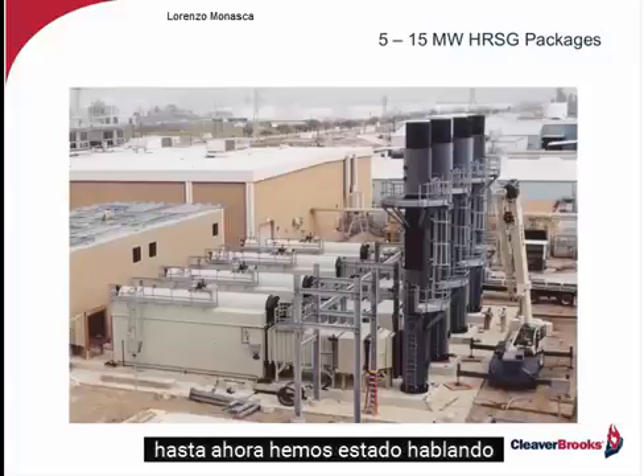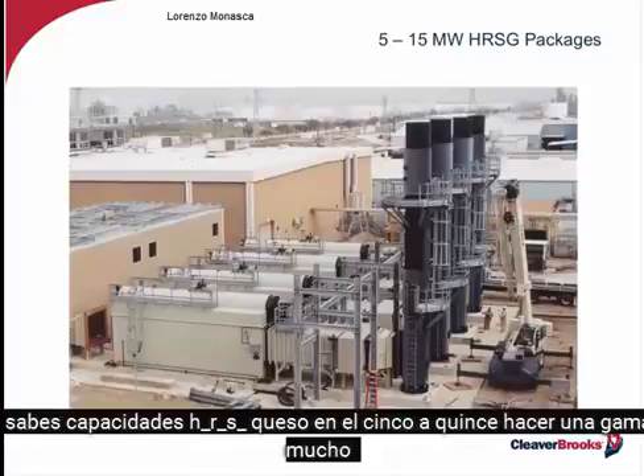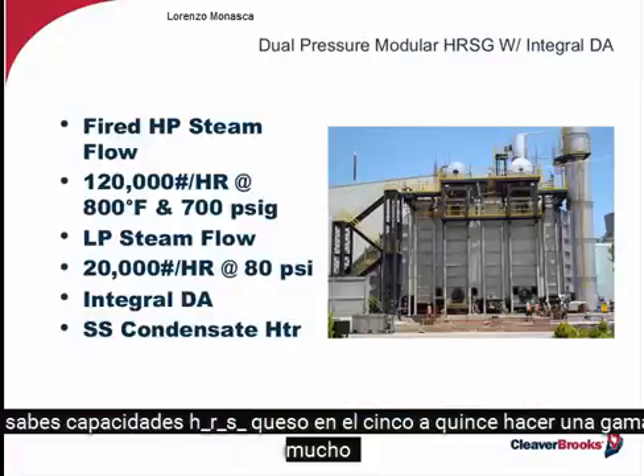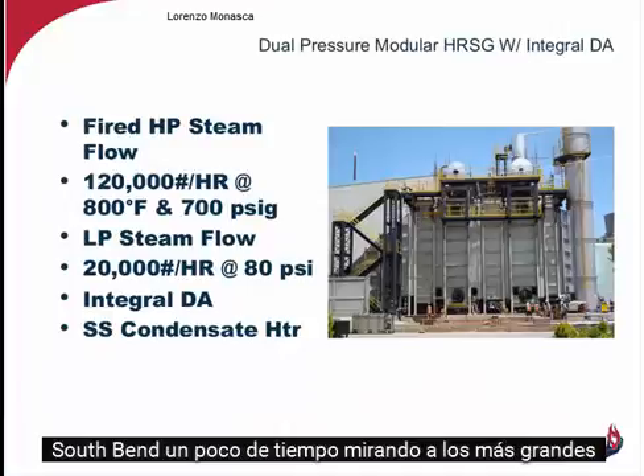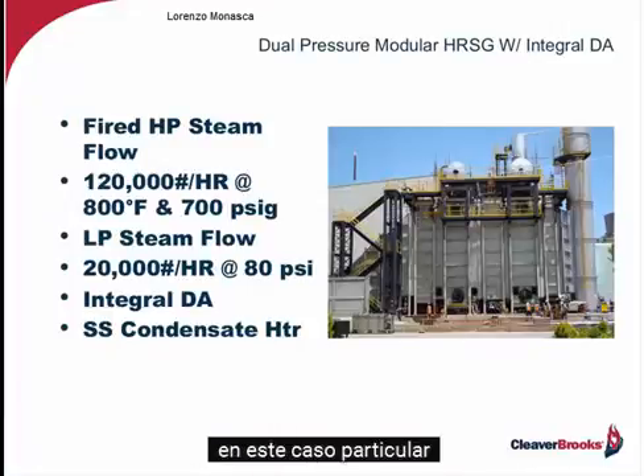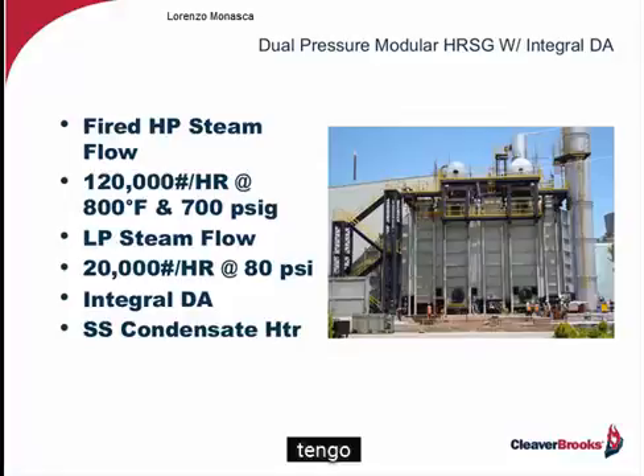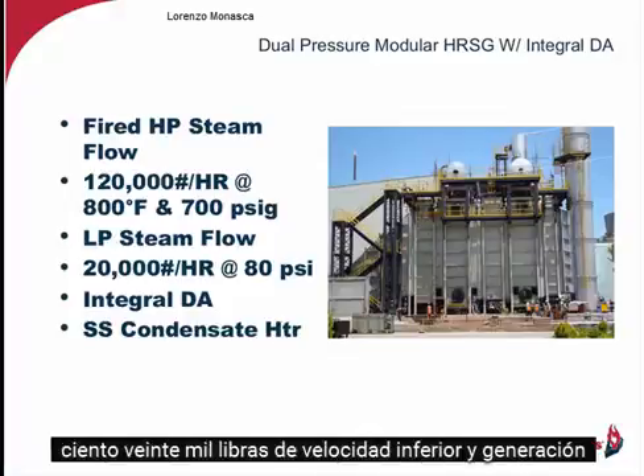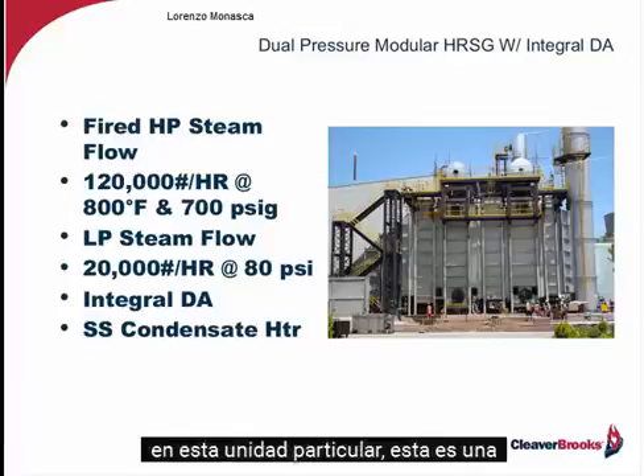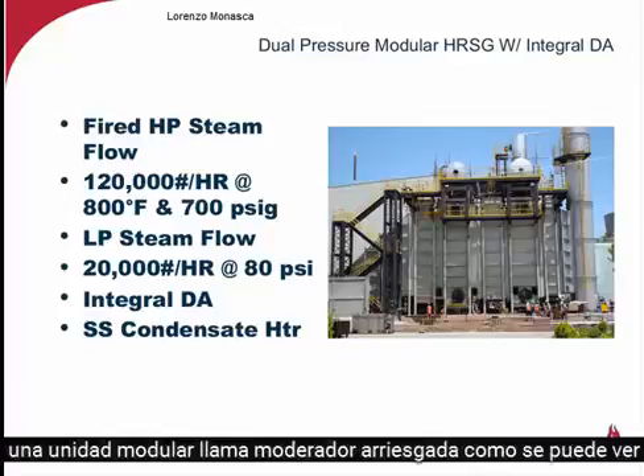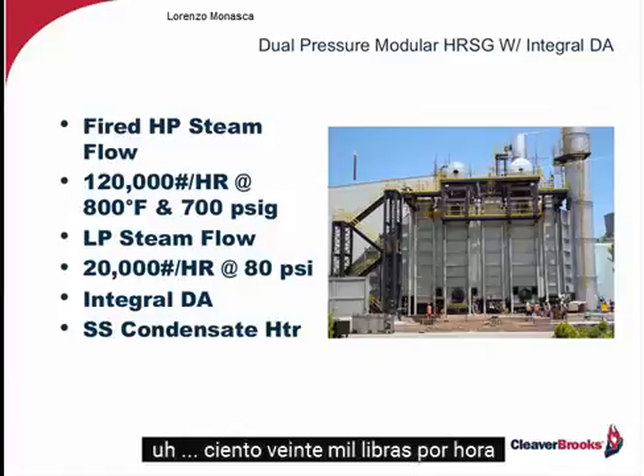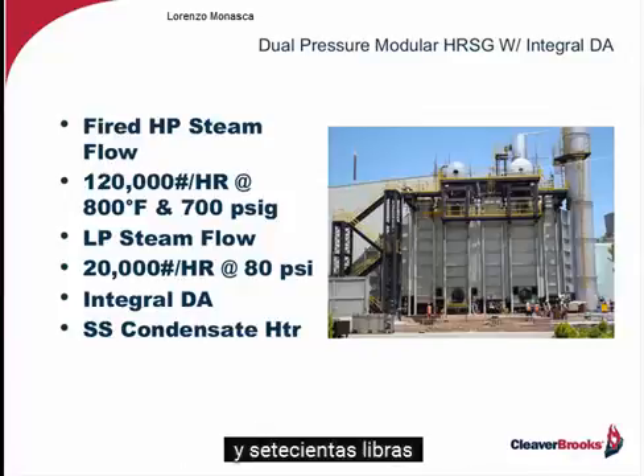So far we've been talking about capacities, HRSGs in the 5 to 15 megawatt range. Let's now spend a little time looking at the bigger ones. In this particular case, I've got 120,000 pounds of steam per hour that I'm generating in this unit. This is a modular unit called a modular HRSG, as you can see. 120,000 pounds per hour at 800 degrees and 700 pounds. That's what I'm generating here.